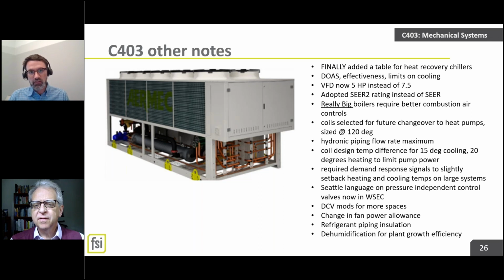Ben? Yeah. The new spiffy one that can run down to really cold temperatures, what kind of temperature water can it produce? Because I've been hearing rumors about a new one that's hitting the market that can produce gas boiler type temperatures. Yeah, they say it can do 180 down to 20-something degrees, and it can do 140. If you're replacing a condensing boiler, you would often run at 140 supply, 120 return. It can run 140 down to like 5 degrees.